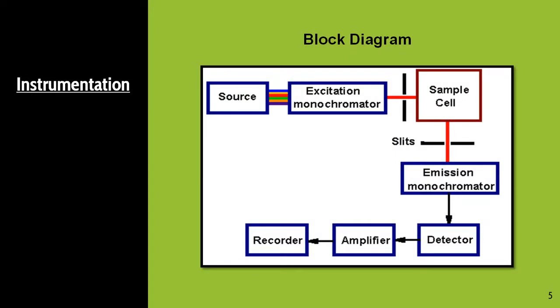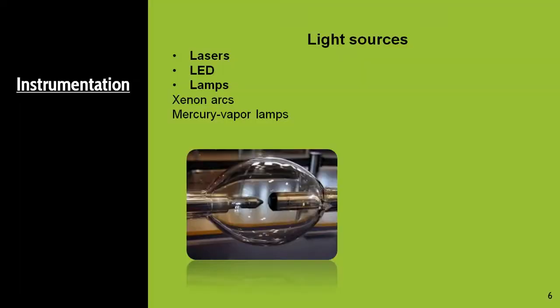Let us see the instrumentation for fluorimetry. This is the block diagram: first you can see light source, then excitation monochromator, then sample cell, then a slit, then emission monochromator, then detector, amplifier, and recorder. Here you can see two monochromators are used, unlike UV — the excitation and emission monochromator. Light sources generally used are lasers, LEDs, and lamps, including xenon arc lamps and mercury vapor lamps.